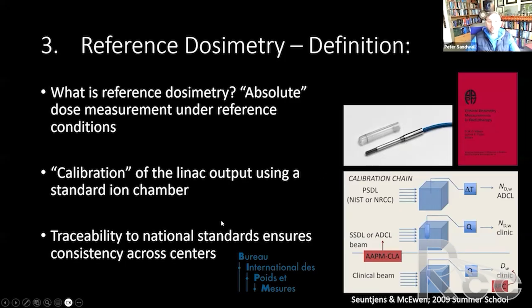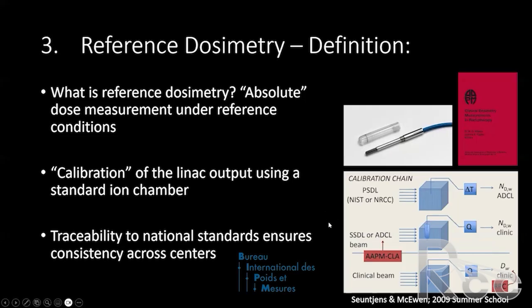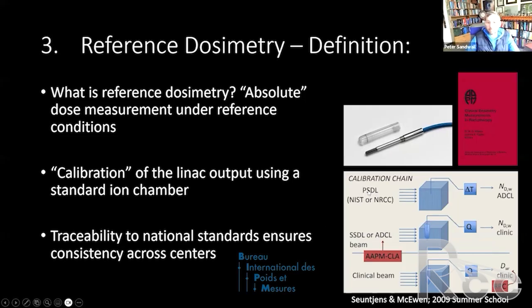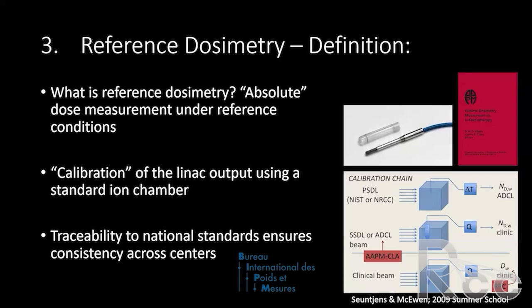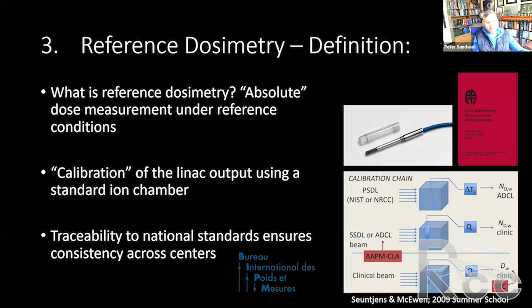That ion chamber is traceable back to national standards. And it actually starts at the Bureau International des Poids et Mesures. And this is in France. Then from this standard, it goes out to different primary dosimetry labs. And then from there, it goes to accredited dosimetry calibration labs. And then from there, it goes to the clinic. There's a chain, and this is where, again, understanding the uncertainty matters. Each time you pass something down, there may be a little bit of uncertainty added, and we do our best to minimize that. But when we get an ion chamber, that typically has from 1 to 2.5% uncertainty in the N_D,W. This is something to consider.